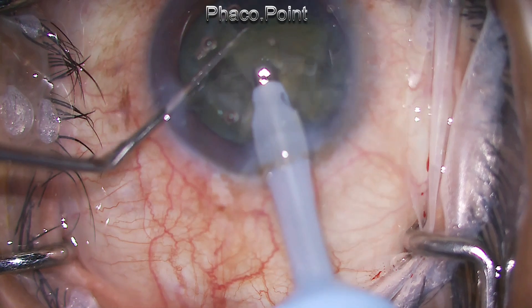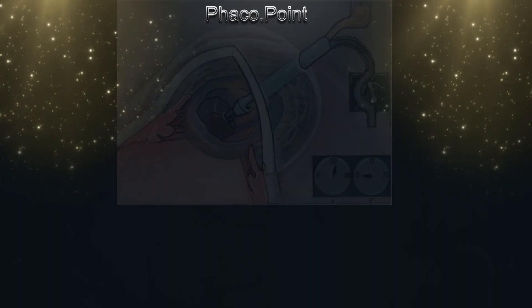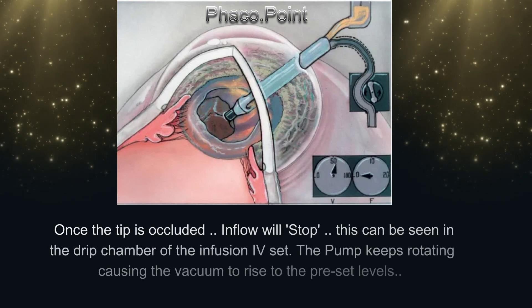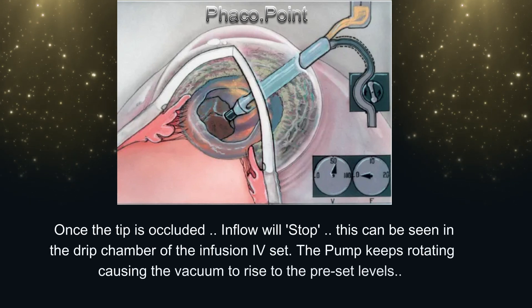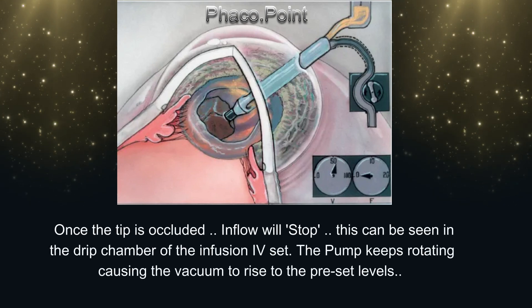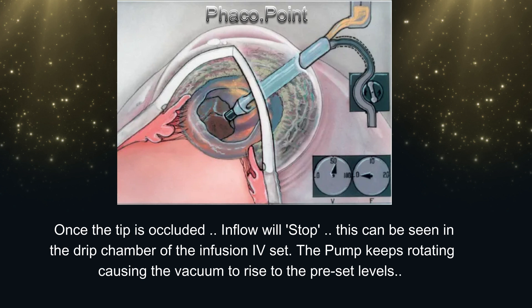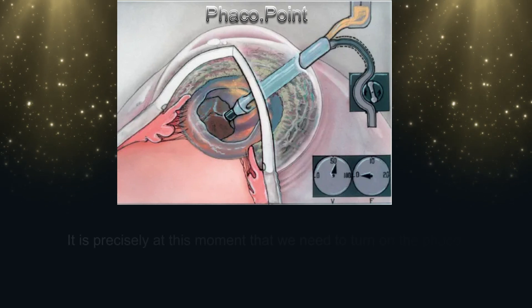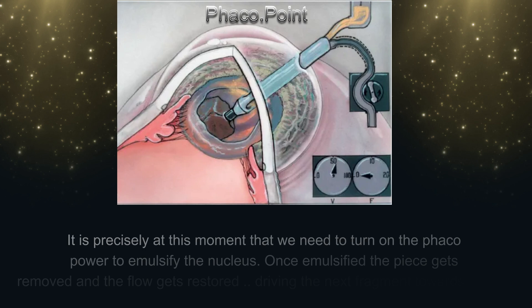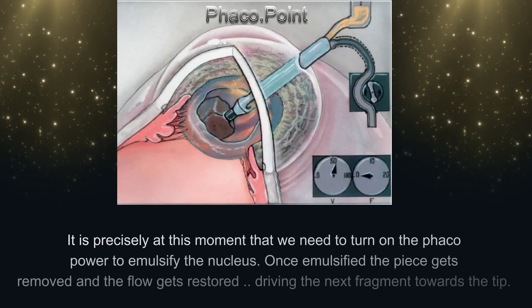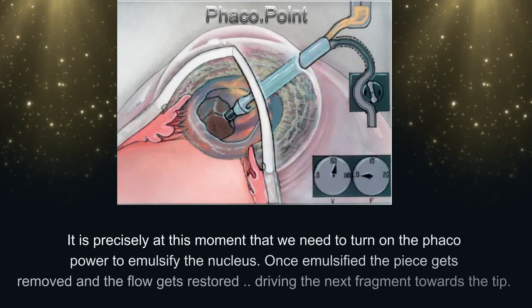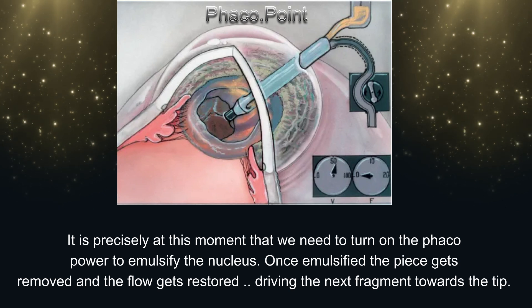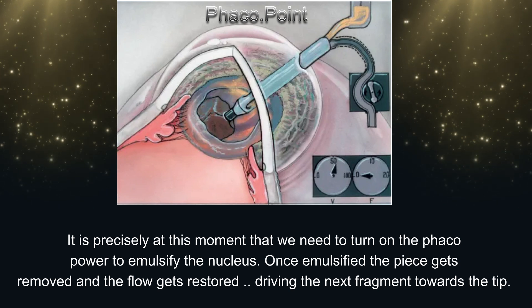Let's look at this in the correct perspective. Once the tip is occluded, the inflow will stop — this can be seen in the drip chamber of the infusion IV set. The pump keeps rotating, causing the vacuum to rise to the preset levels. It is precisely at this moment that we need to turn on the phaco power to emulsify the nucleus. Once emulsified, the piece gets removed and the flow gets restored, driving the next fragment towards the phaco tip.